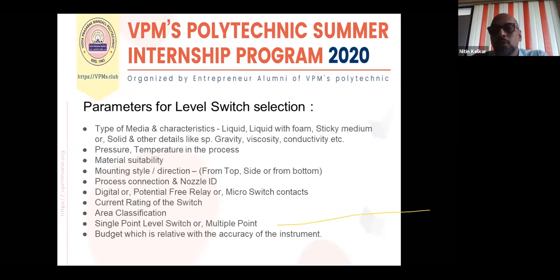Area classification, what I mean is whether it is a hazardous area, or just a weatherproof, dustproof area. Again, selection on that basis is very important, because in hazardous areas, if a standard weatherproof model is used, at the time of operation there is always a very fine spark, and this spark can cause an accident. It can cause an explosion also. So there are types of enclosures selected depending on the area classification.